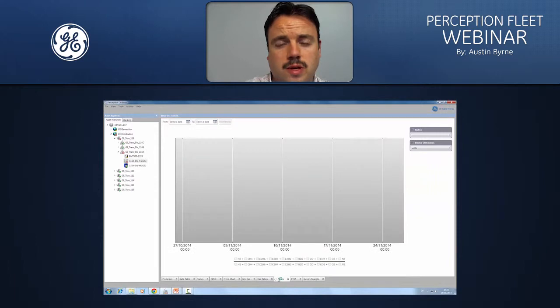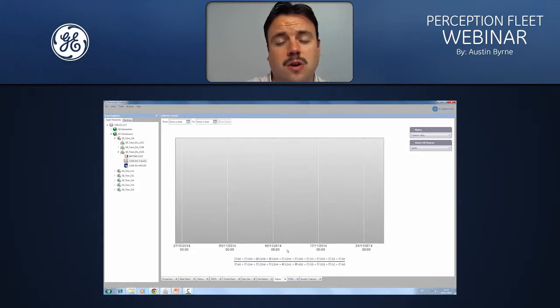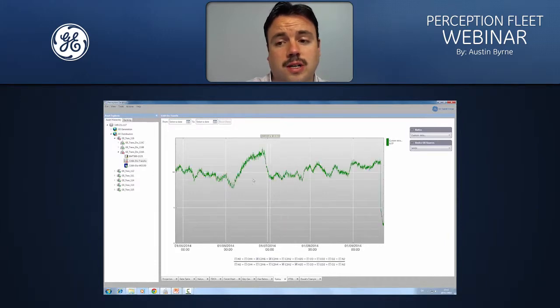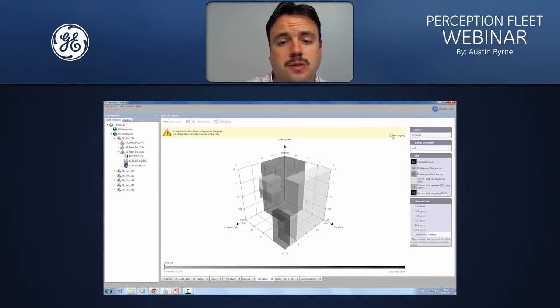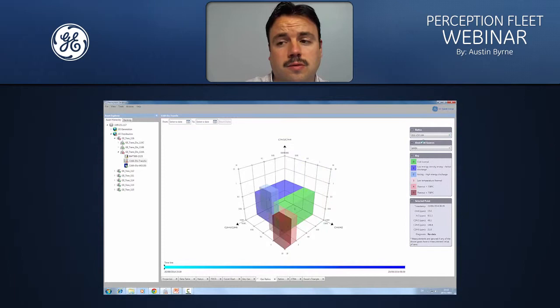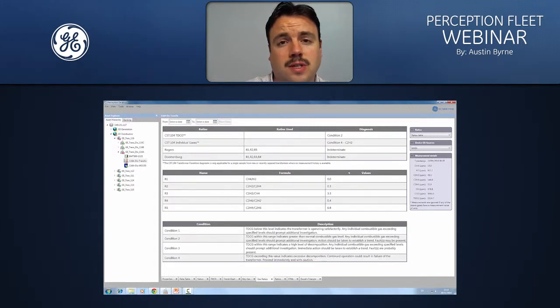our ratios. One of the other features in Perception in the workbooks is that you can create on-the-go ratios. So I can tick the gases that I want to compare, and Perception will automatically generate a real-time ratio calculation of those gases and display it in the chart, as you can see here. Then we have our gas ratios, which is our Duval's and Rogers ratios comparative. You can see I can select the IEC 60599 or the IEEE ratio, and I can also go into a table that tells you exactly what you're looking at in terms of the visualization in the cube. These are the ratios used in those particular diagnostics, and what their formulas are, and what the condition statements and the descriptions of those conditions are.